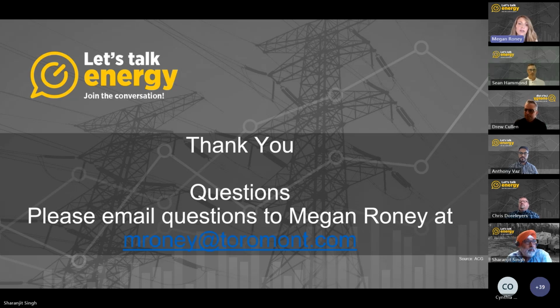So we did get a question for Anthony: could you elaborate more on the generator working capacity with the best efficiency? Can it run at 100% capacity? Yes, that's a great question. Technically, a generator can run at 100% capacity, but that's not quite ideal for long-term use. The best efficiency, as we mentioned in the webinar, is typically around 70 to 85% load. That's where fuel use, wear, and performance are all optimized. So when an integrator is sizing a generator for a microgrid, the balance is struck between not having the generator maxed out and not having it underloaded. An integrator would take all these aspects into account when reviewing the system for the best reliability, efficiency, and overall performance.